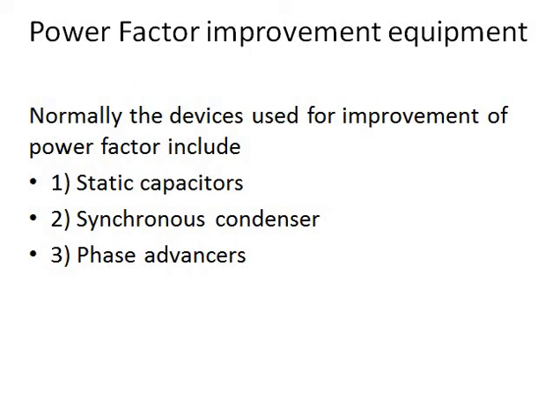Further, making use of synchronous condensers. Now the problem with synchronous condensers is that they are very large in size and they make continuous noise. So although it's an improvement technique, it also comes with some drawbacks. There are also some drawbacks with static capacitors, like they pose a problem during switching.